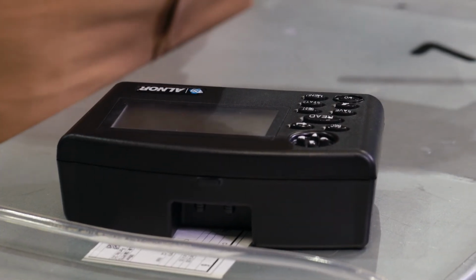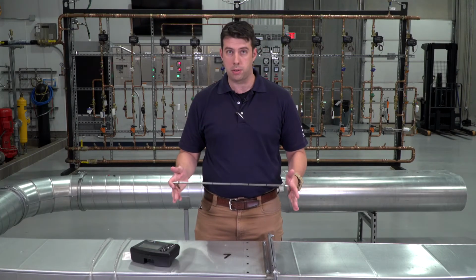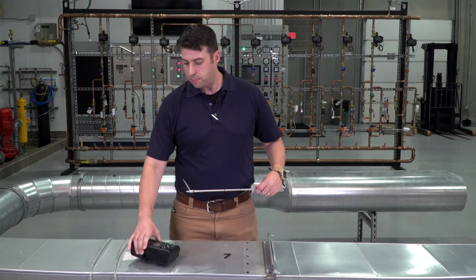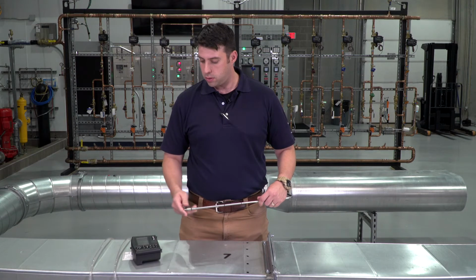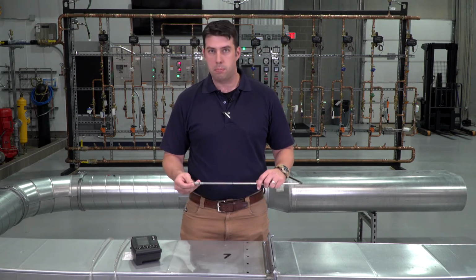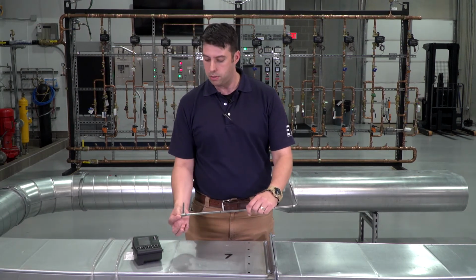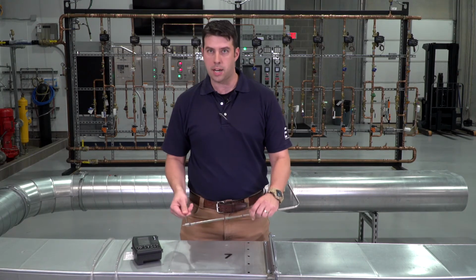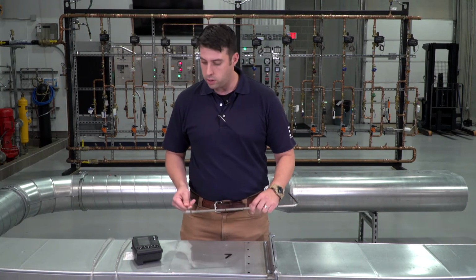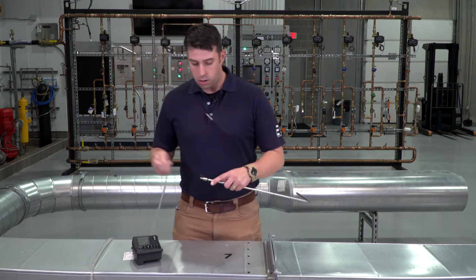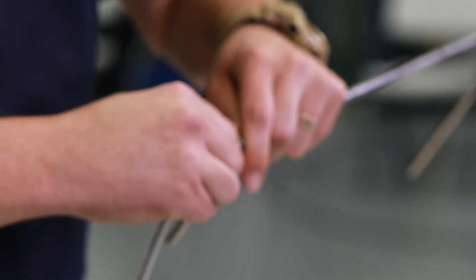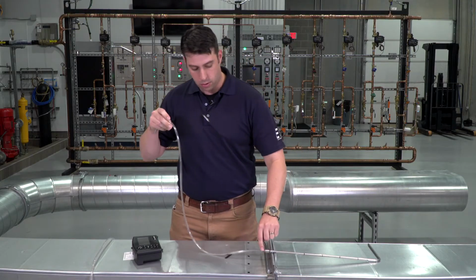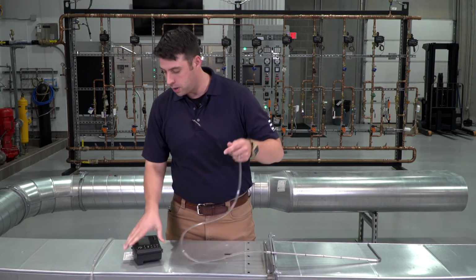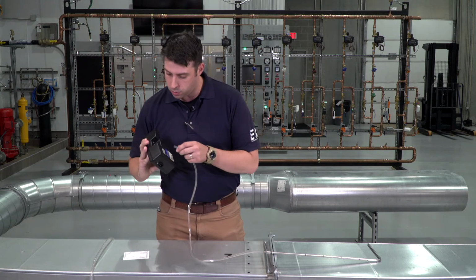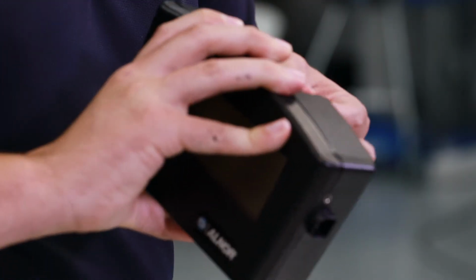Okay, now we are going to connect our manometer to our pitot tube. Again, the manometer is utilized here to accept the pressure from the total pressure port of the pitot tube and the static pressure port of the pitot tube. So let's go ahead and hook that up. We take our hose and ensure that we are nice and snug on our port here. This now becomes our total pressure tube, and we'll ensure that it is hooked up to the positive side of our manometer.